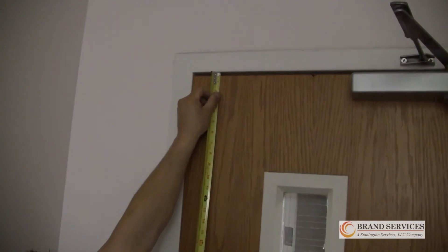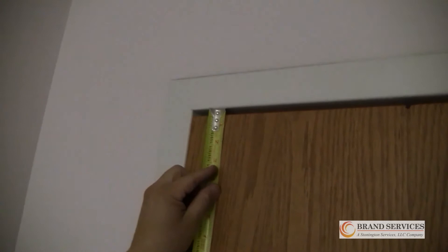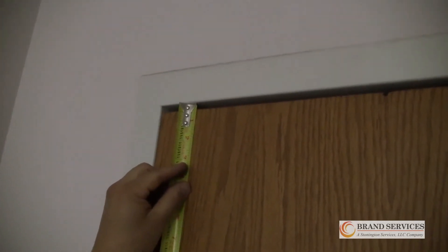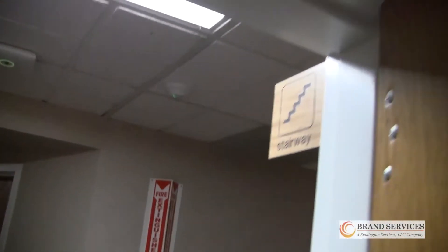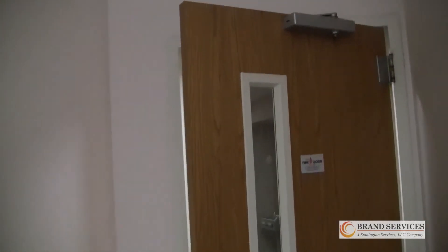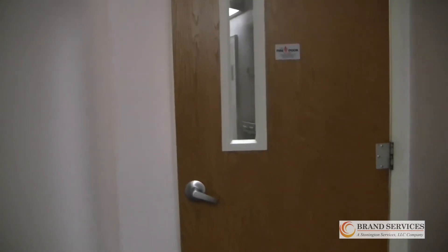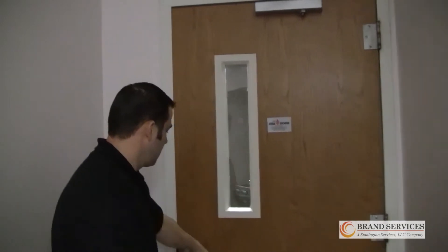The top of the door clearance does not exceed one eighth of an inch. We check the full operation of the door to make sure that the door opens fully to 90 degrees. We check the overall condition of the frame to ensure that no holes or breaks exist and no field modifications have been performed to the frame or door. We have the door at 90 degrees, we let the door go — the door should be positive latching and self-closing. Pull on the handle and verify that the door did positively latch.